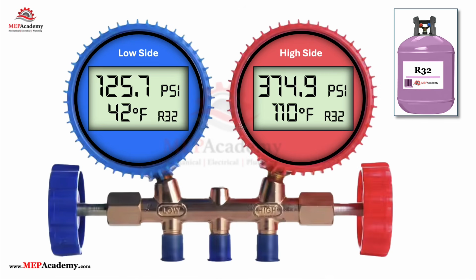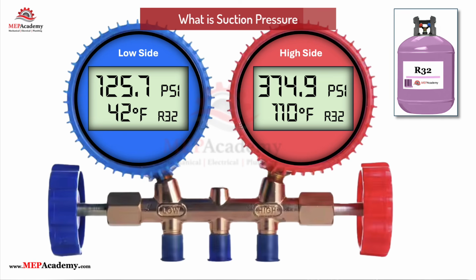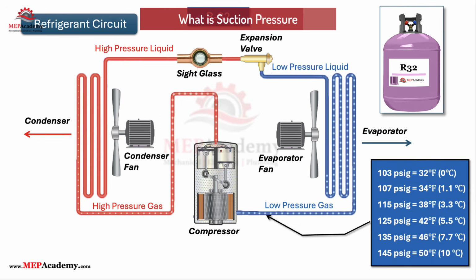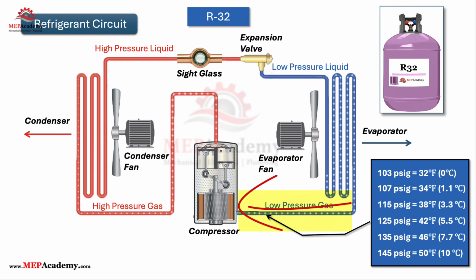Today, we're diving deep into the causes and consequences of low suction pressure in HVAC and refrigeration systems. What is suction pressure? Suction pressure refers to the pressure of the refrigerant vapor entering the compressor from the evaporator. This pressure tells us a lot about what's happening on the low side of the system, particularly in the evaporator coil and the refrigerant lines leading back to the compressor.